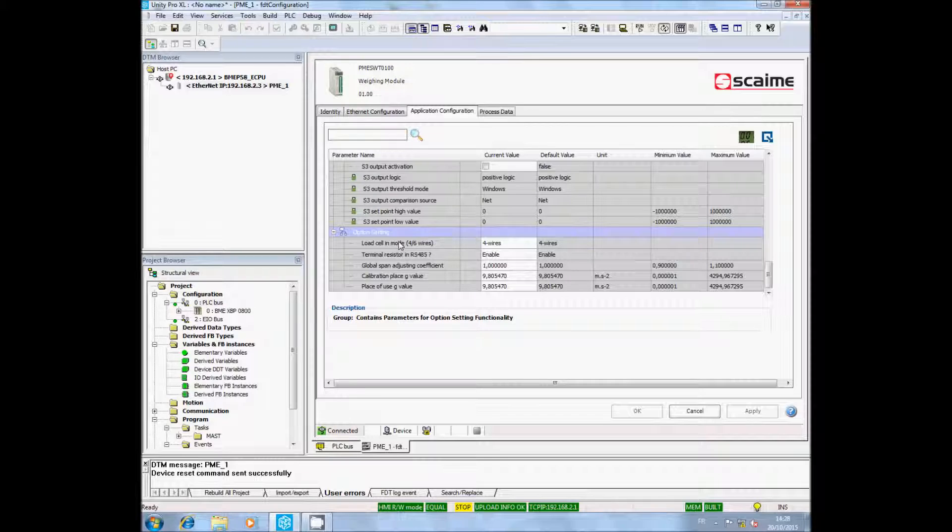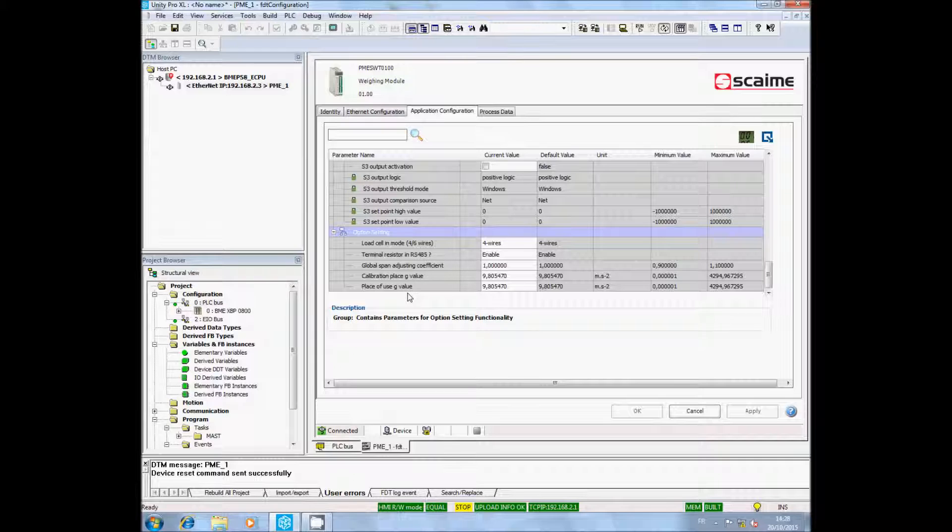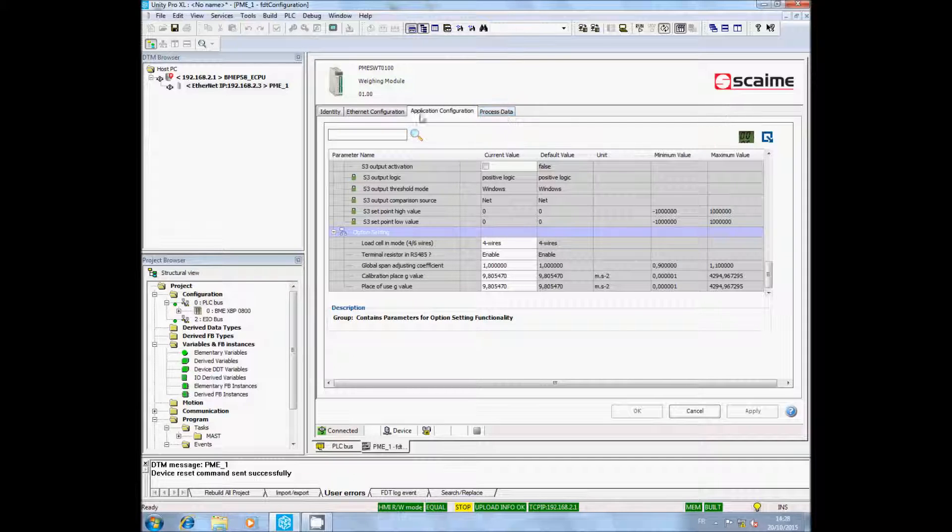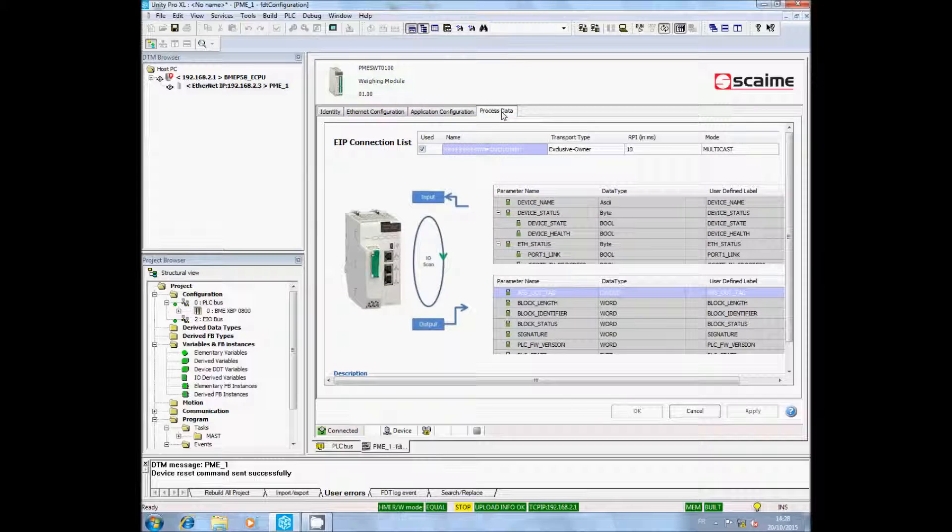In this example, I work with a 4 wires load cell, so the configuration is OK. You can also access the name of the PME variables.